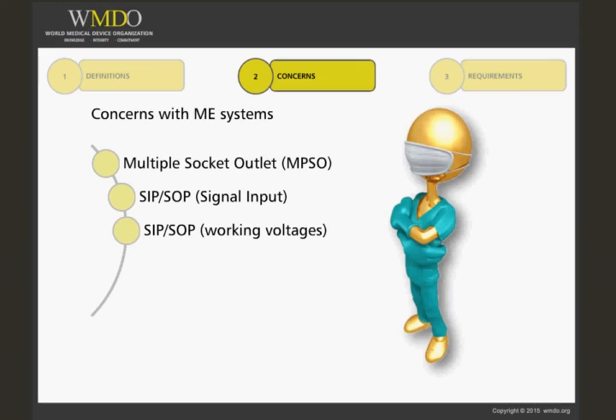For example, if you have an Ethernet connector on your medical device, you must consider the worst-case voltage in normal condition and single-fault condition that can come in through that connection point, and provide adequate electrical isolation for the voltages that could appear on those SIP-SOPs.